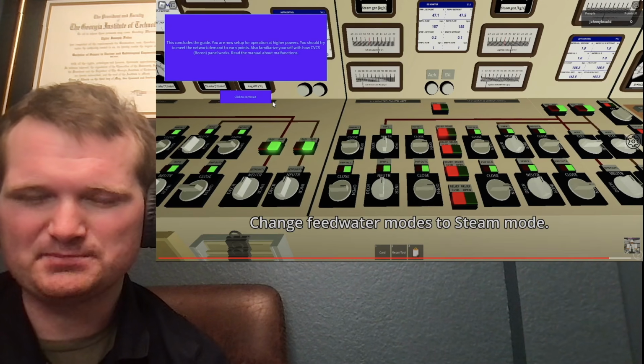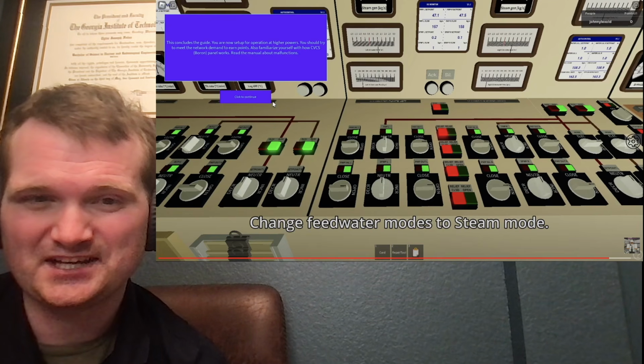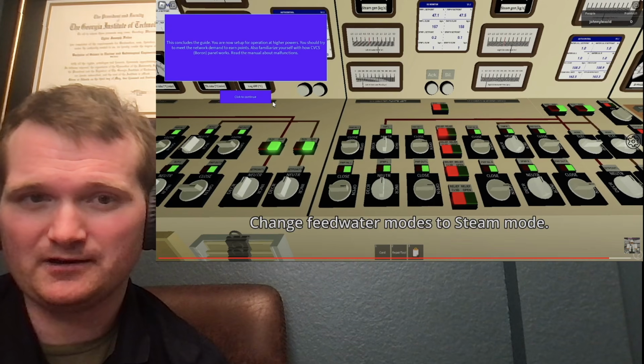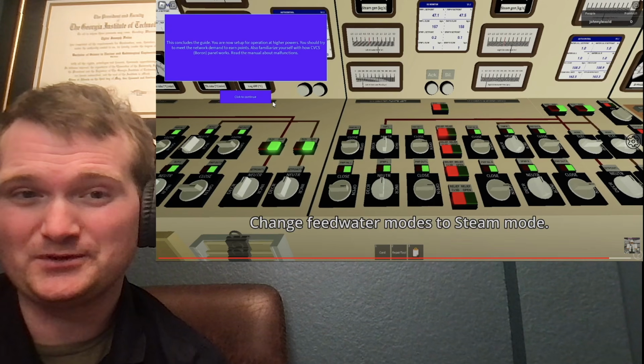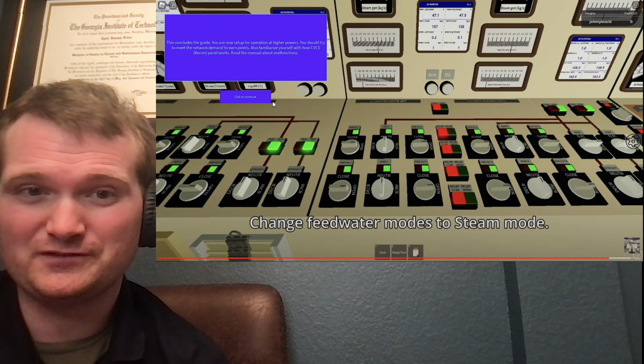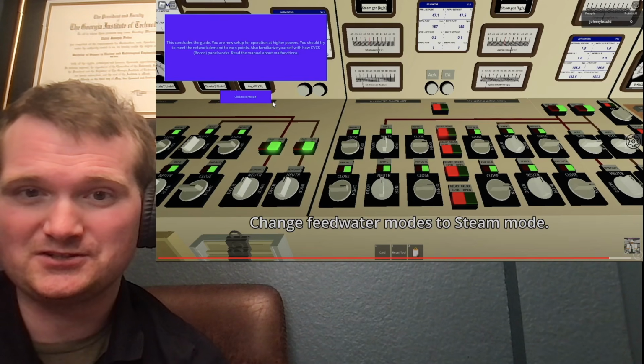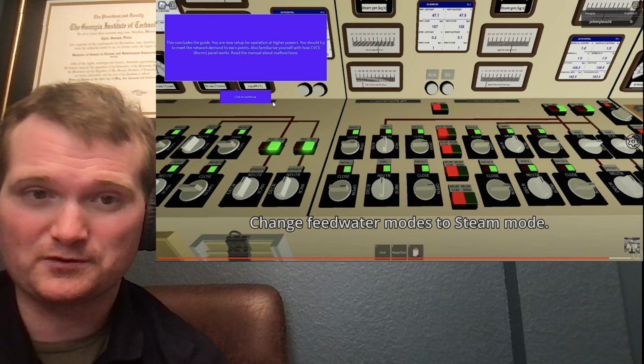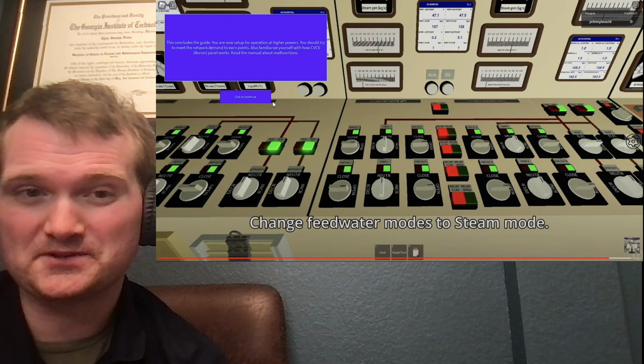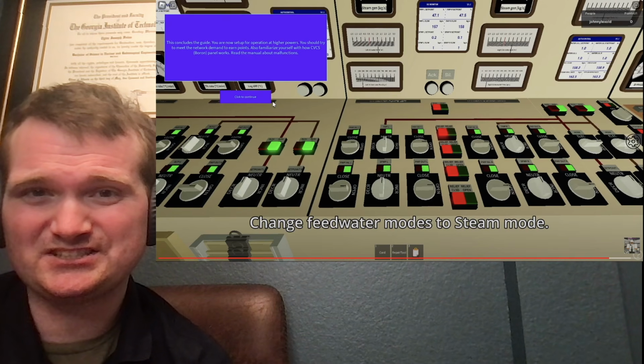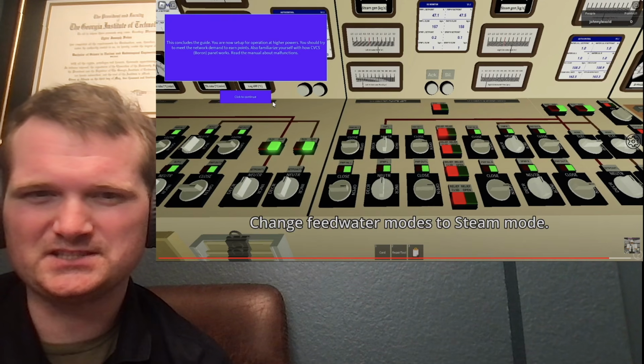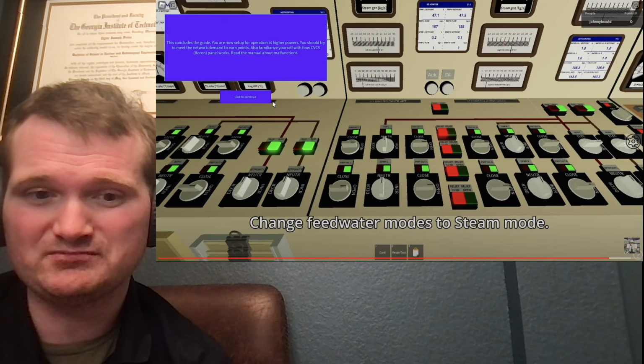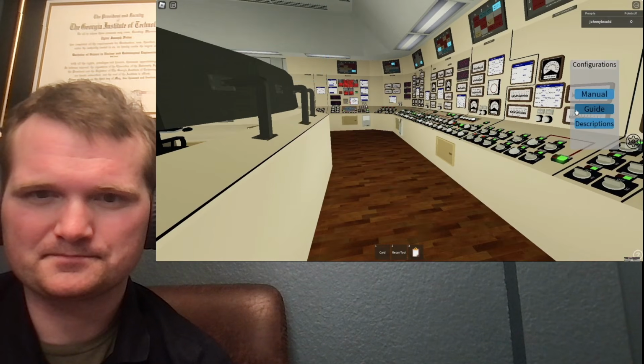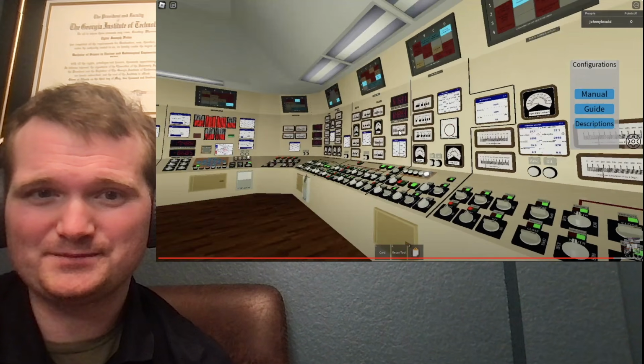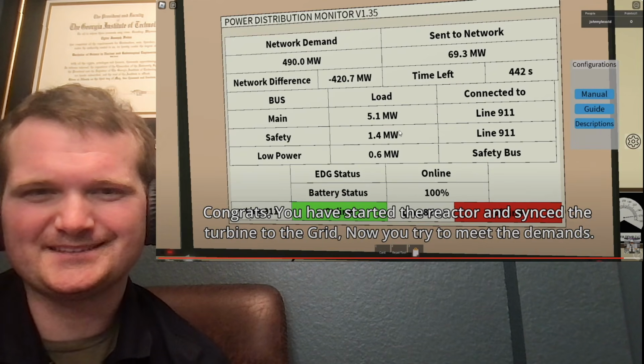As you raise power at various plateaus, 30%, 50%, 60%, they're going to turn on these pumps and start forward feeding with it, because you're making so much more steam, so you're going to want to have that additional feed flow, and to maintain your steam pressure and feed pressure, differential pressure, in order to ensure a smooth startup and operate smoothly. It's pretty easy, it's just something you need to plan ahead for. I've actually done that specific job as well, being the reactor operator that ran the secondary, and just like anything else, just plan ahead. And there you have it. They'll continue to go up and just ramp up to 100%, where they'll just be turning on more and more things. So congrats, you've now started the reactor.